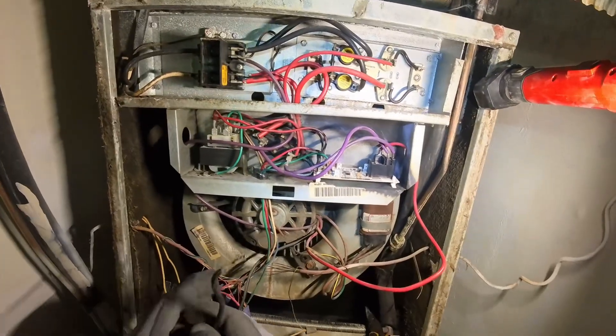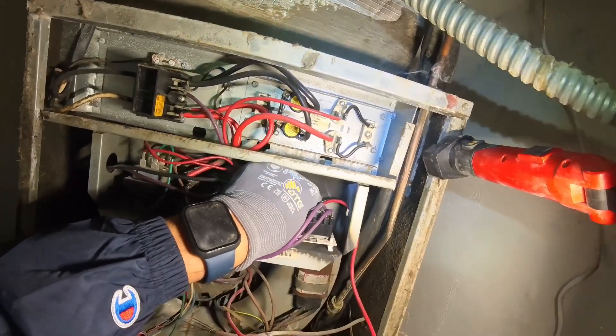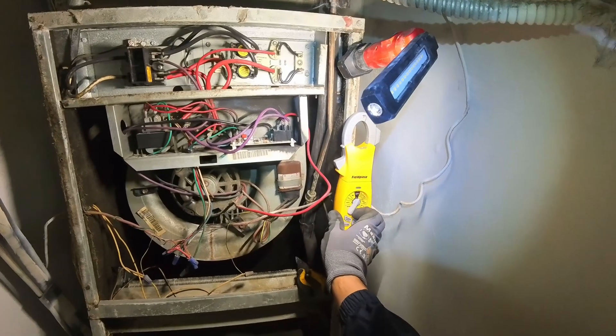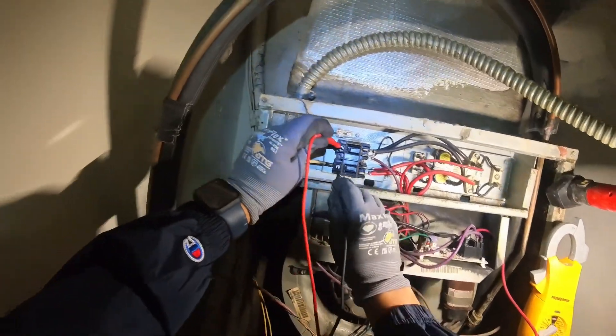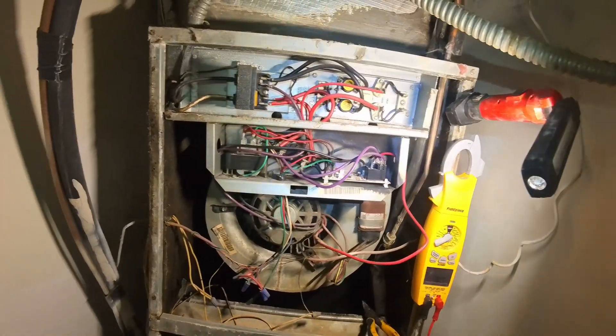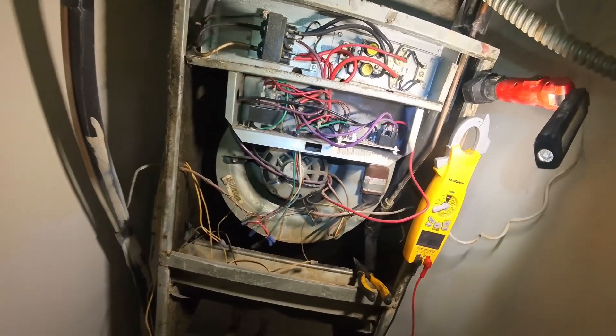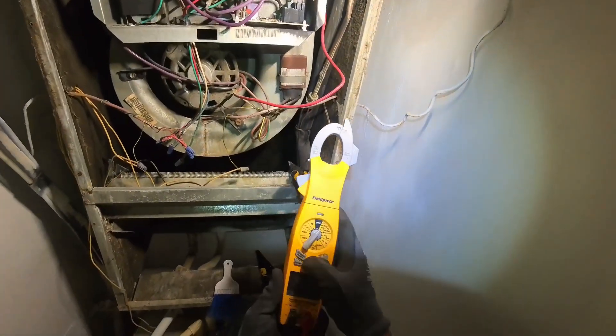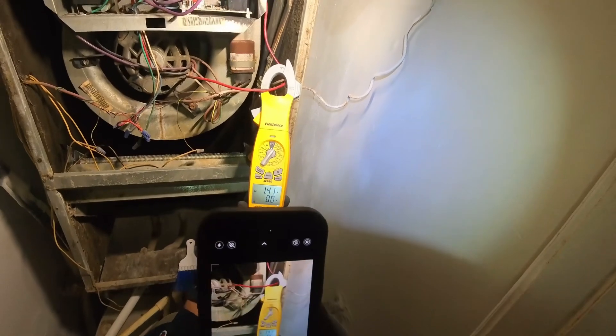Let's put this one on park. About to go turn on that breaker. Let's turn this on — I got the fan on already. We'll see what it does. There's our fan. So I'm going to go back to the thermostat and put it on emergency heat. 1.40 amps. Our outdoor unit is running in heat mode. I went ahead and put it in heat mode because I know I'm not going to get good pressures with this cold weather out here.